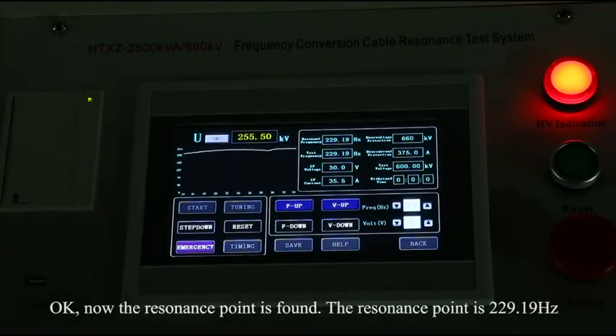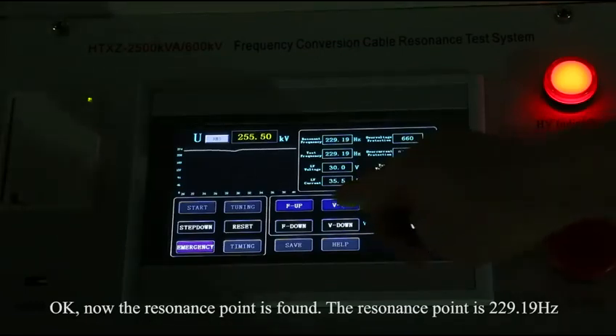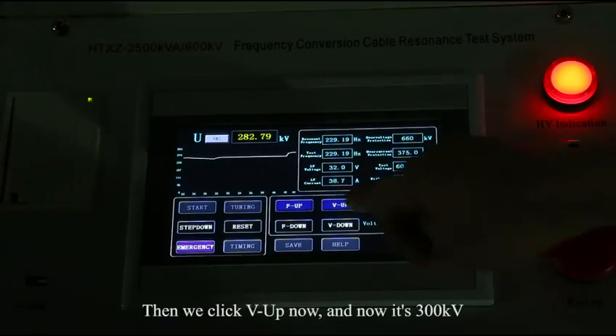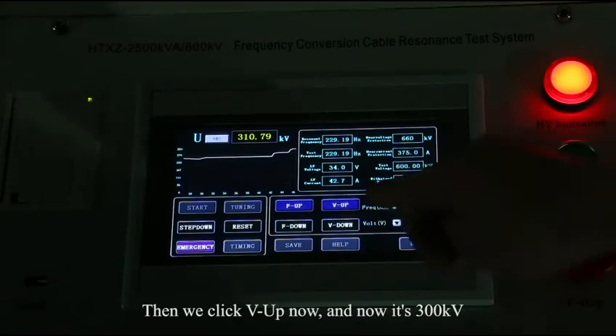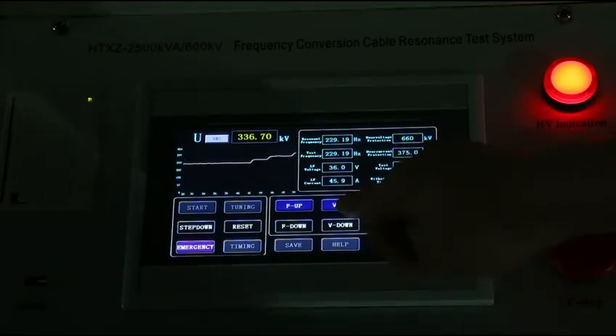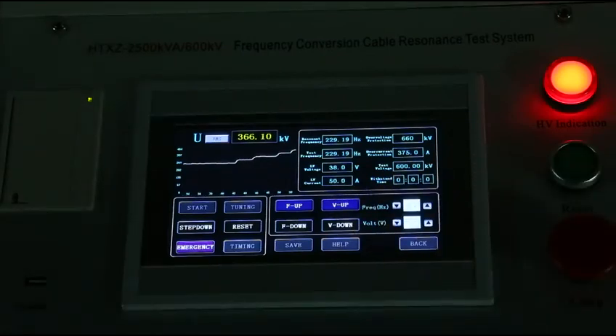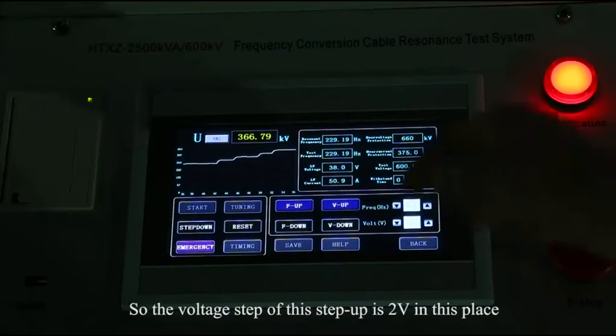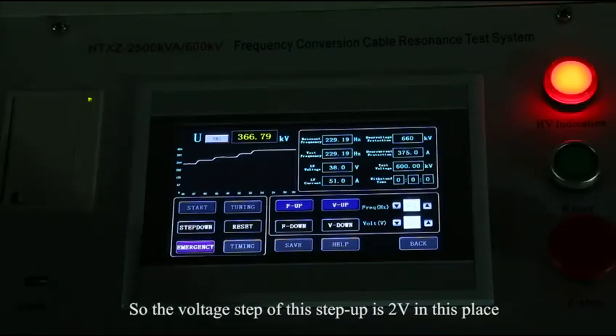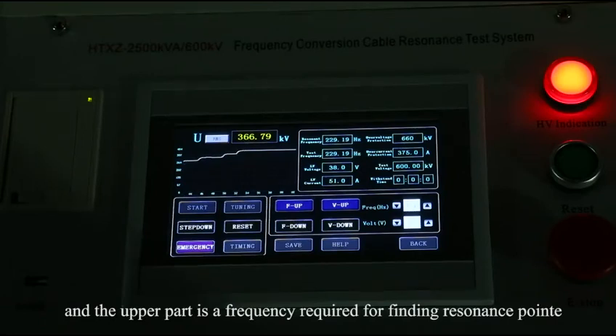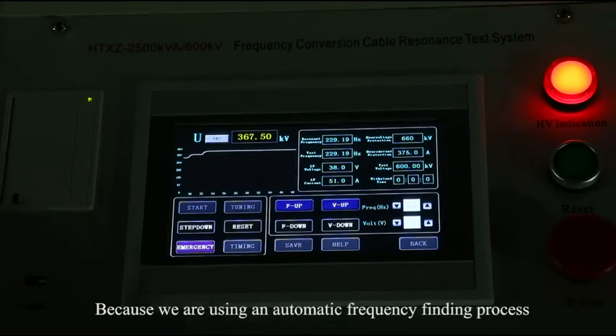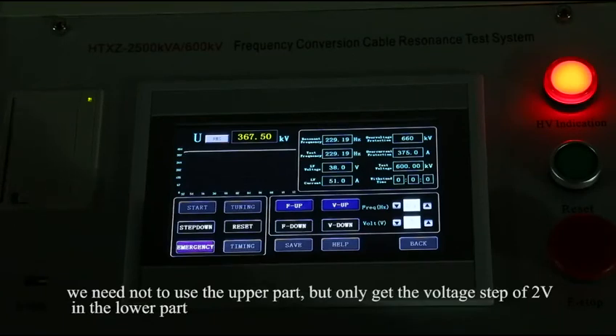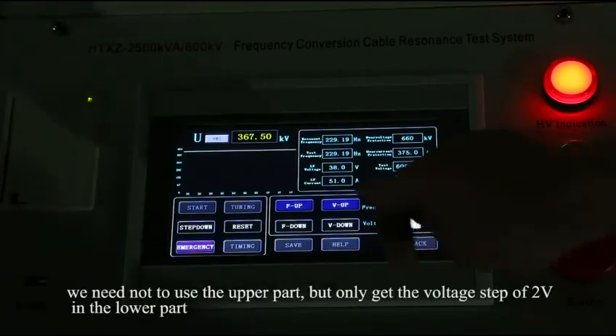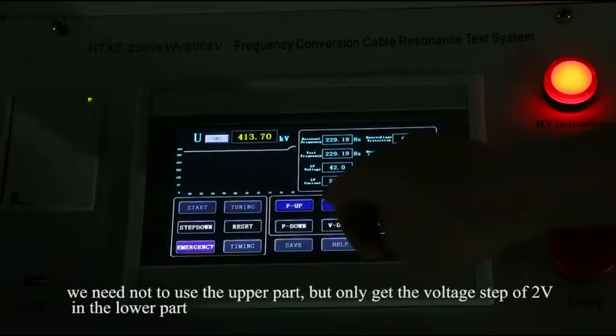Okay, now the resonance point is found. The resonance point is 229.19 Hz. Then we can click V up, and now it is 300 kV. So the voltage step of this step up is 2 volts in this place, and the upper part is the frequency required for finding the resonance point. Because we are using an automatic frequency finding process, we did not use the upper part, but only use the voltage step of 2 volts in the lower part.